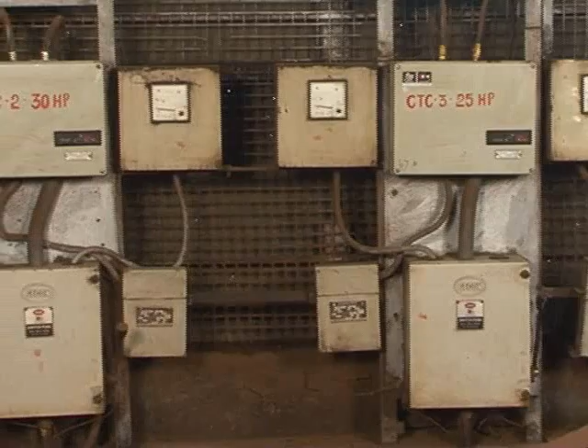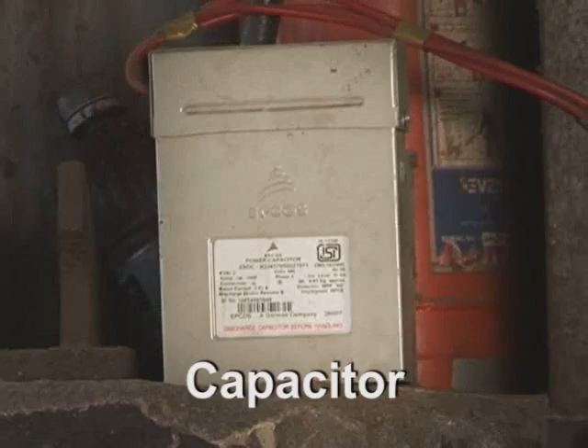I am glad to share the experience of Kaikati factory, which is a cooperative government factory, about the demand control that it has exercised very efficiently through installation of capacitors. By having a fixed 140 kVA demand, we are able to control the cost by the constant cost on kVA demand cost, and also we are able to control escalation above this sanctioned demand by installing the capacitors at 3 different levels, one at the section level and the individual motor level, and then we also have common automatic power factor control.